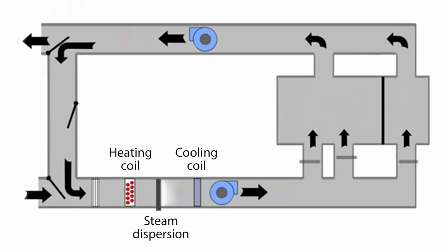Sometimes people like doing that because if you do get any moisture carry over, hey, there's a cooling coil with a drain pan. And so that may be a good choice. But you have to consider if you're going to be doing humidification and cooling, if it comes across a cool surface, you may remove some of that moisture you've just added. If you're not going to do both those processes, then that'd be just fine. Otherwise, going after the cooling coil would be just fine.